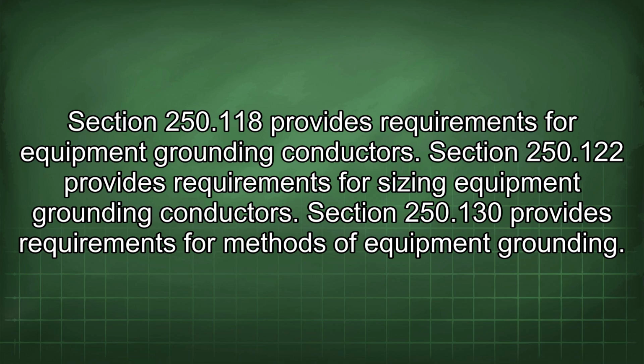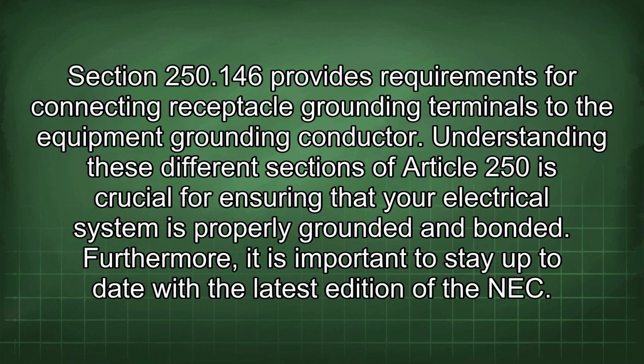Section 250.122 provides requirements for sizing equipment grounding conductors. Section 250.130 provides requirements for methods of equipment grounding. Section 250.146 provides requirements for connecting receptacle grounding terminals to the equipment grounding conductor.